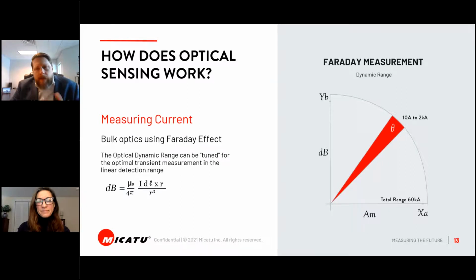If you think about how Faraday's principle works, it's pretty straightforward. You have a piece of glass that reacts in a magnetic field. We shoot a photon through this, and the way the photon comes back out changes, and that change is proportionate to the actual current, which is proportional to the magnetic field. One of the exciting things about Faraday measurement is that we have a huge dynamic range.